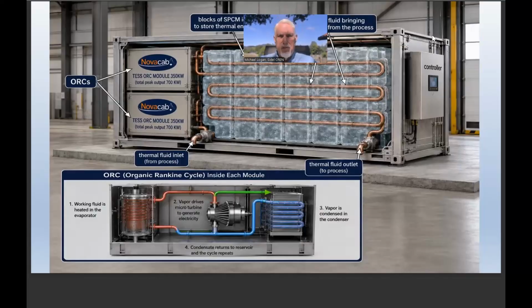This is the TESS. I mentioned ice a little bit earlier. You see the blocks of ice in the 1 megawatt TESS, storing 3.5 million BTUs. There's copper tubing that runs through this programmed ice, and then you can see the converters, which are organic Rankine cycle engines. Each is able to put out 350 kW, totaling 700 kW. And if we have the thermal energy to back it up, we can do that 8760 hours all year long.